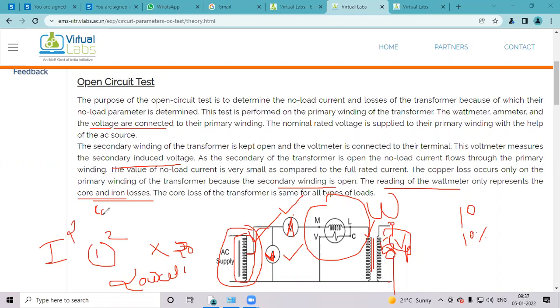So the core loss of the transformer is the same for all types of load. These losses, the core loss, will not change, meaning it is constant. If you put the load again or conduct a load test, the constant losses will remain constant for all types of load, whether it is resistive load, inductive load, or capacitive load. So for all types of load, these losses remain constant.